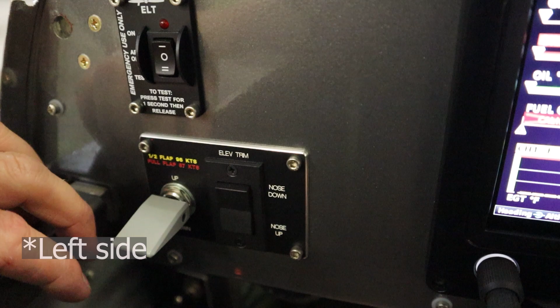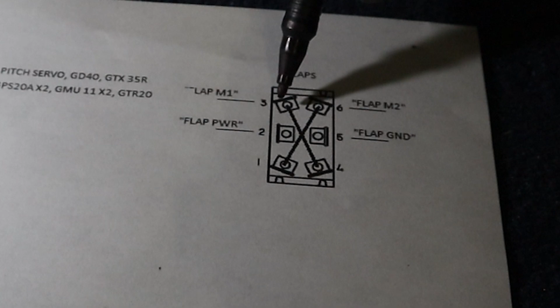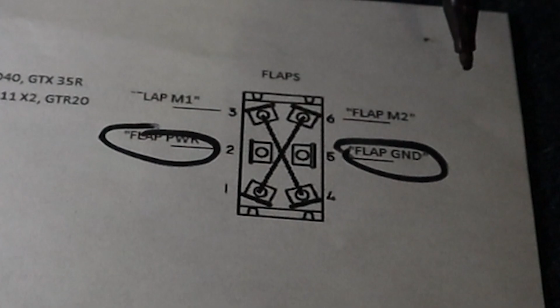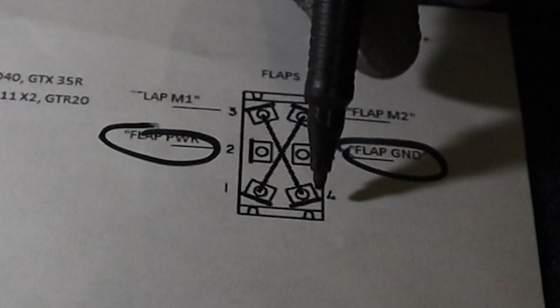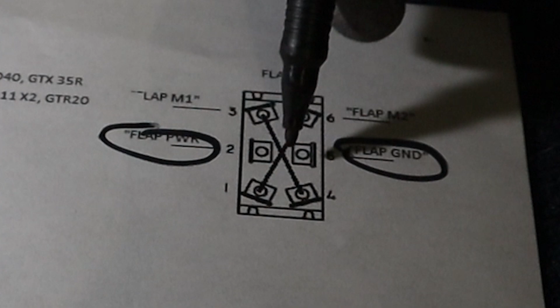How that's wired is from the EarthX battery, it's going to send out a ground signal. So this one is a little different than the two other lights, in that when there's an actual battery fault, the EarthX sends out a ground signal. That goes to the ground side of this, and you wire the other side of this battery fault light to actual power - so battery fault. If you look at the fuse panel, we actually have a fuse called bat light power. That's how those lights are going to work on the top there.